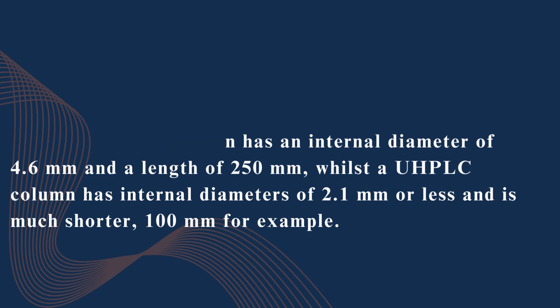Column dimensions. As with particle sizes, there is a corresponding reduction in column dimensions with UHPLC. A typical HPLC column has an internal diameter of 4.6 mm and a length of 250 mm, whilst a UHPLC column has internal diameters of 2.1 mm or less and is much shorter, 100 mm, for example.